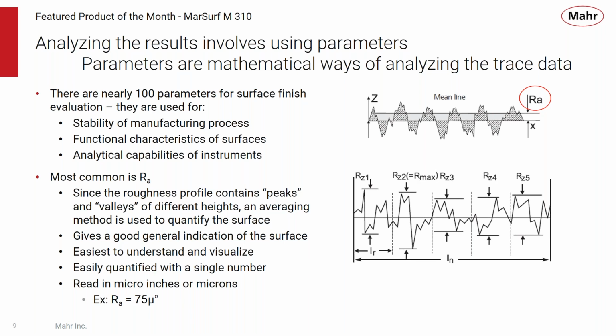And when talking about the basic parameters of roughness, RA is the most common way of measuring a surface. Since the roughness profile contains peaks and valleys of different heights, an averaging method is used to quantify the surface. Now, this gives a good general indication of the surface. It's easiest to understand and visualize, and it's easily quantified with a single number. So it can be read out in micro inches or microns. An example of a roughness might be the RA equals 75 micro inches. So that gives the user a nice, simple way of quantifying what that surface is.